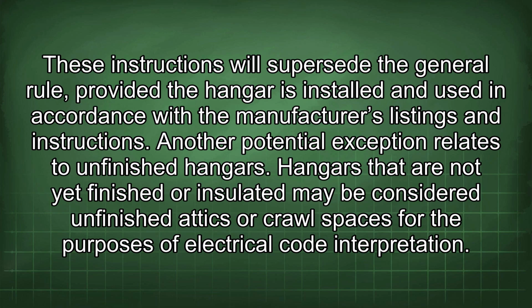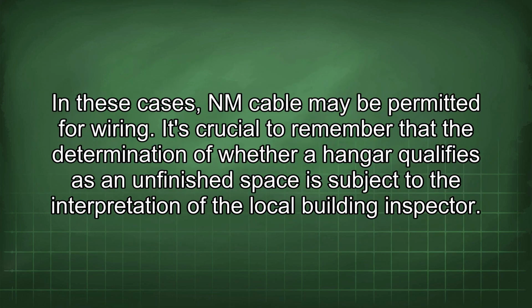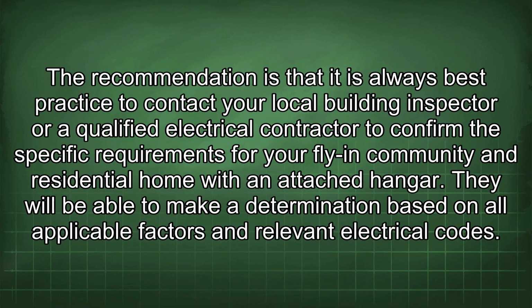Hangars that are not yet finished or insulated may be considered unfinished attics or crawl spaces for the purposes of electrical code interpretation. In these cases, NM cable may be permitted for wiring. It's crucial to remember that the determination of whether a hangar qualifies as an unfinished space is subject to the interpretation of the local building inspector. The recommendation is that it is always best practice to contact your local building inspector or a qualified electrical contractor to confirm the specific requirements for your fly-in community and residential home with an attached hangar. They will be able to make a determination based on all applicable factors and relevant electrical codes.